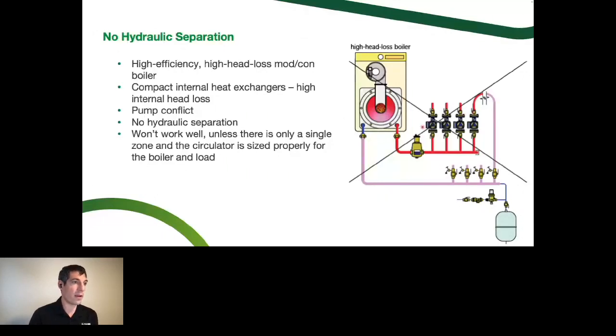There's a problem here. We now have 4 different circulators that could come on and off. This heat exchanger in a mod con is going to be more picky about the flow rate that it wants. That's why a lot of the modulating condensing boilers just ship either with a circulator in the cabinet mounted already or in the box ready to plug in, because we don't want to leave this up to chance. We don't want to have some wide range of flow rates that could be 5 GPM or could be 20 GPM. We want to make sure that we've got a very specific flow rate through that boiler. This isn't a big 20-gallon cast iron boiler with a lot of buffer capacity and a lot of volume that we can just kind of send a huge range of flow rates through. It's going to short cycle. It's going to have a hard time if we're below the minimum flow rate. It's going to go to post purge and come back on. It's not going to work very well.